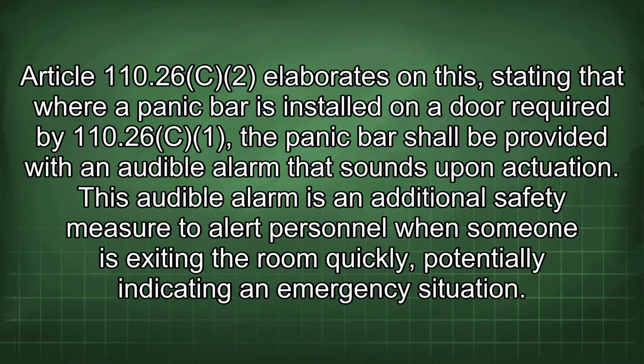Article 110.26(C)(2) elaborates on this, stating that where a panic bar is installed on a door required by 110.26(C)(1), the panic bar shall be provided with an audible alarm that sounds upon actuation.